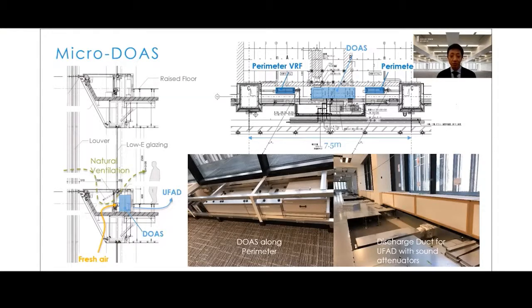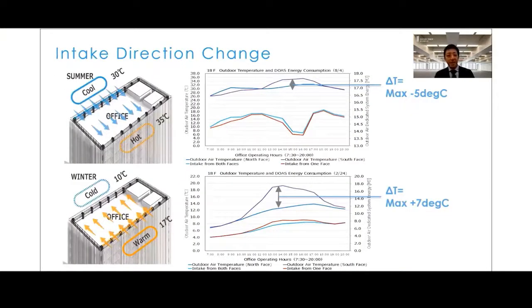It is estimated to contribute to a reduction of water-air conveyance energy by more than 30% compared to a traditional central DOAS system. Underfloor air distribution was introduced to effectively distribute air from the system, especially in heating season. Taking advantage of the outdoor temperature difference, mainly caused by absorption of direct solar radiation at the south side and shading at the north, the direction of the outdoor air intake is automatically switched to further minimize the load. In summer, lower temperature air is taken from the north, and vice versa in winter. The result of post-completion measurement shows a significant effect, as a temperature difference of 5 degrees was achieved during the peak summer and 7 degrees C during the peak winter.